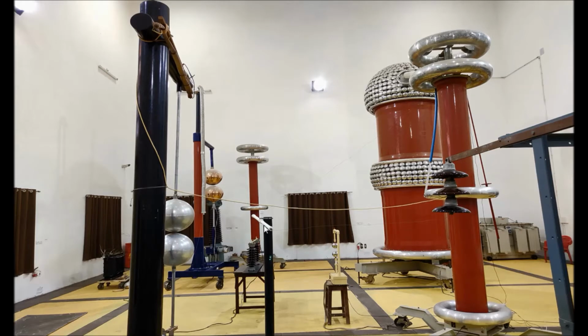Then the transformer output is connected to this point. This white one, you can see, is the water resistance. Why have I used a water resistance? Because it limits the short circuit current. The output of the water resistance is connected to the insulator. You can see this wire is connected to the insulator. This point is grounded, and this metal frame is totally grounded. Then you can apply the voltage to the string. That means this is the voltage across the whole string, because this is the high voltage point and this is the ground point.